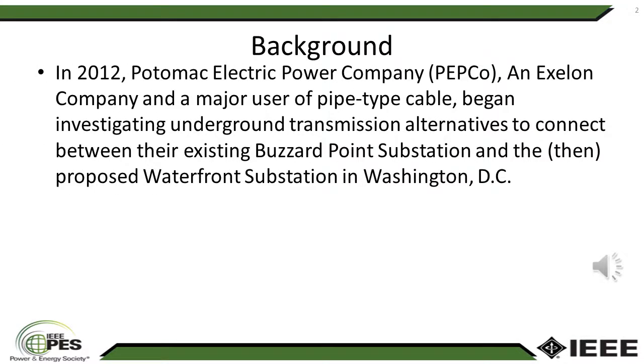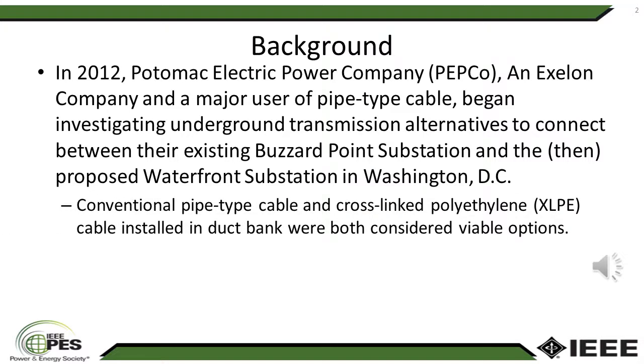In 2012, the Potomac Electric Power Company was investigating alternatives for connecting their existing Buzzard Point substation to the proposed new Waterfront substation, both located in Washington, D.C. Conventional pipe-type cable or cross-link polyethylene cable installed in duct banks were both considered viable options.